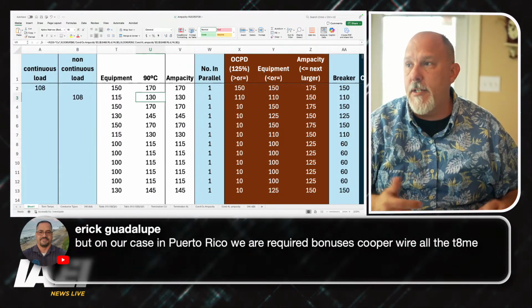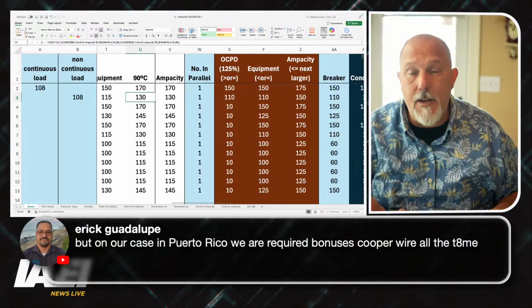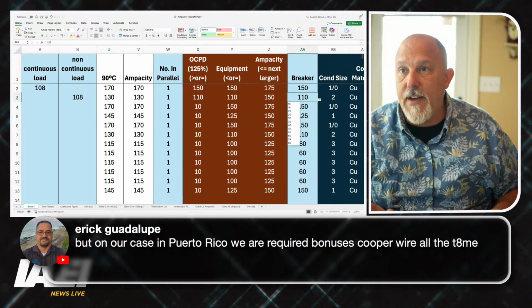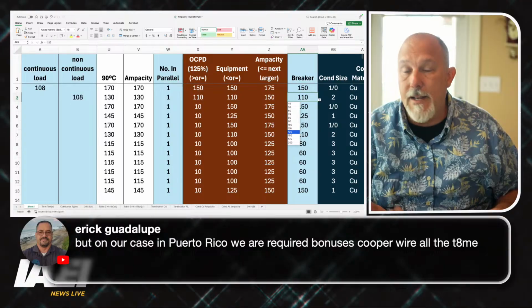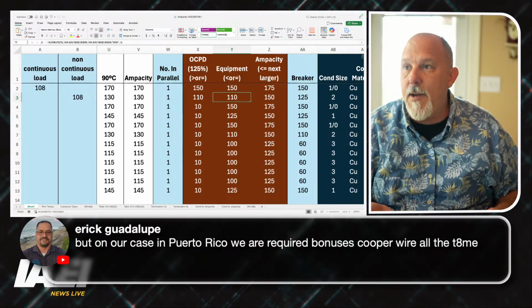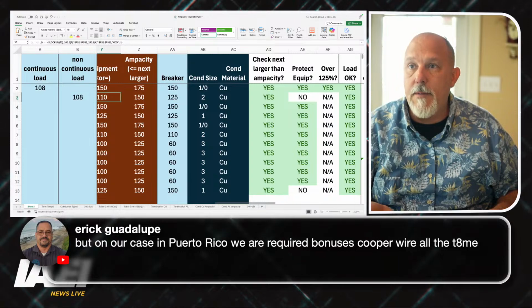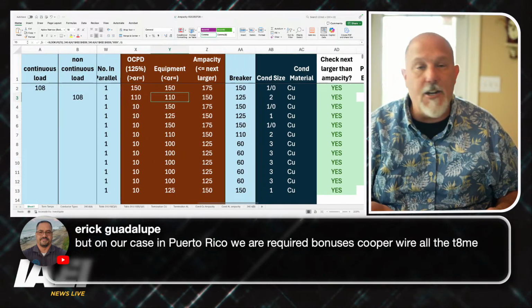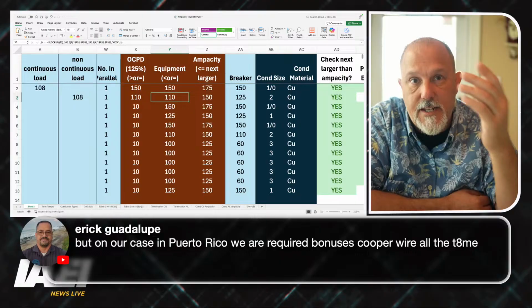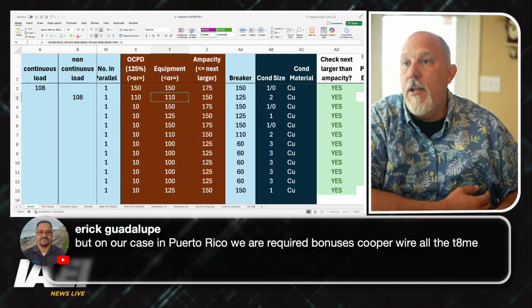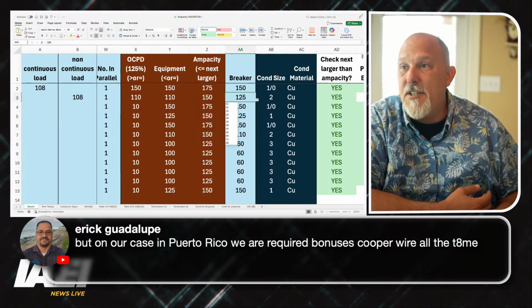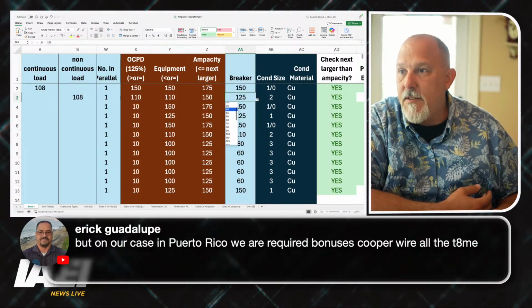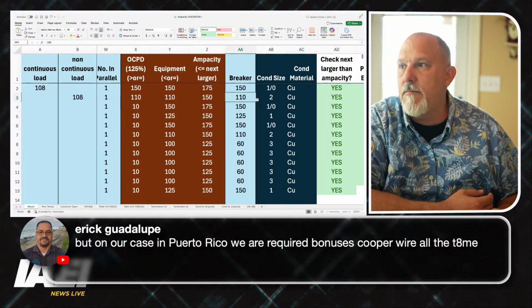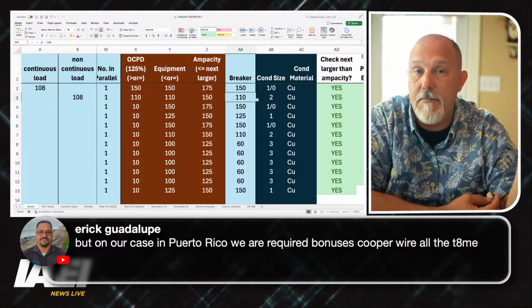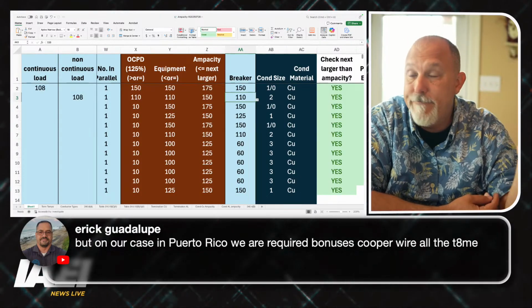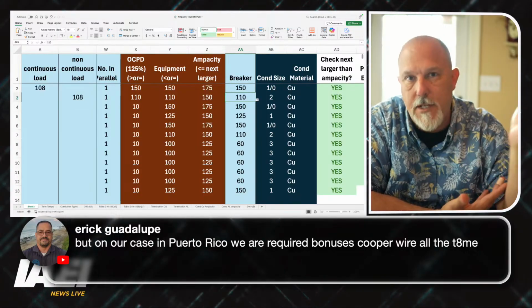Now, could I put a larger size? Could I go to 125? No, I can't. If I go to 125 amps, the next larger size, now I'm not protecting the equipment. I'm exceeding the 110 amps, which is based on the 75 degree C column. And you wouldn't go there anyway. Why? Because you'd be buying a larger overcurrent protective device than what you need. And who wants to, well, wait a second. If you want to send money my way, please do. But if you don't need to, you don't have to.